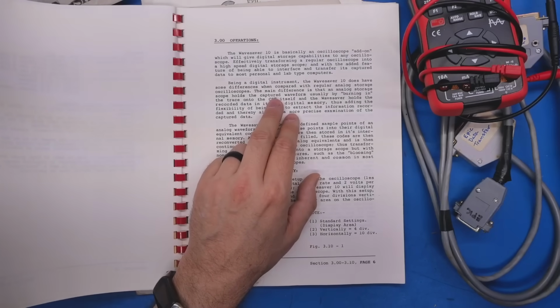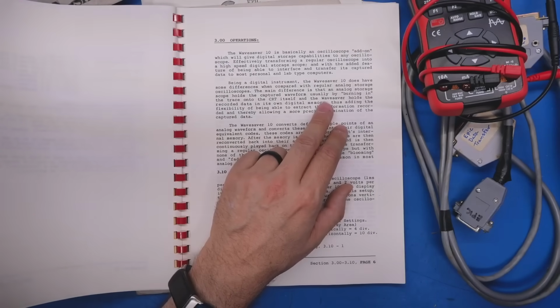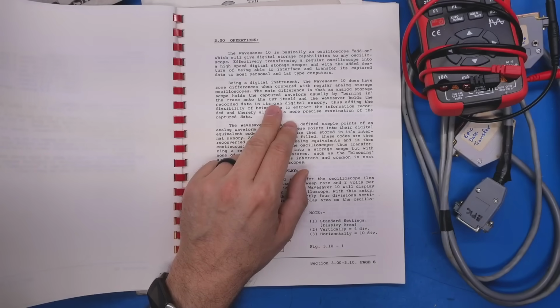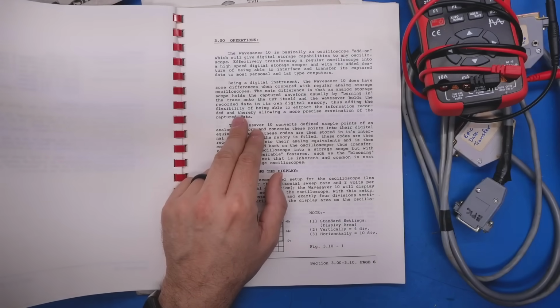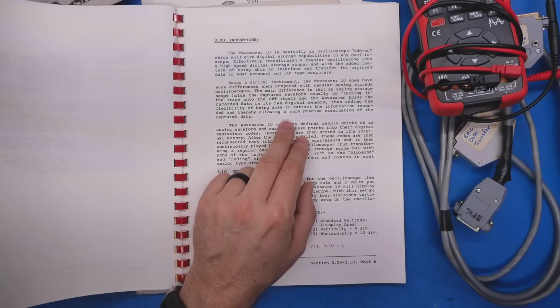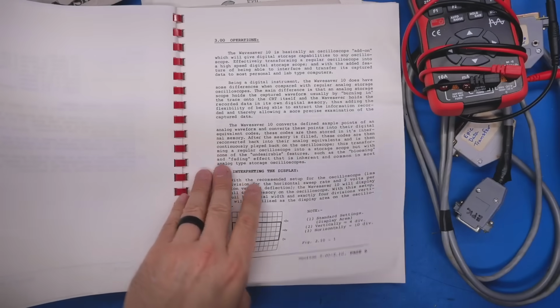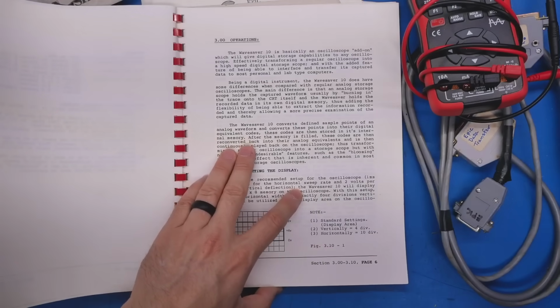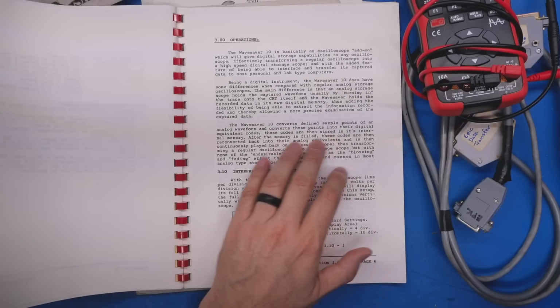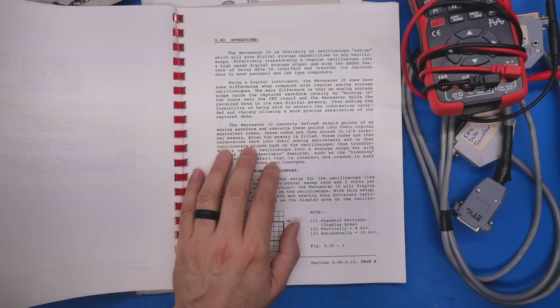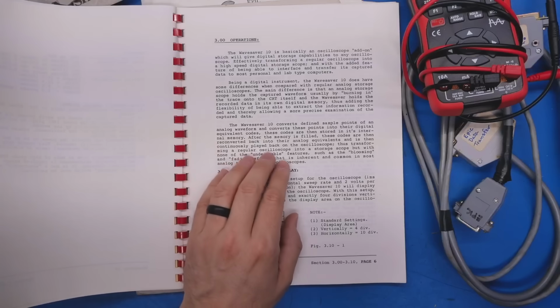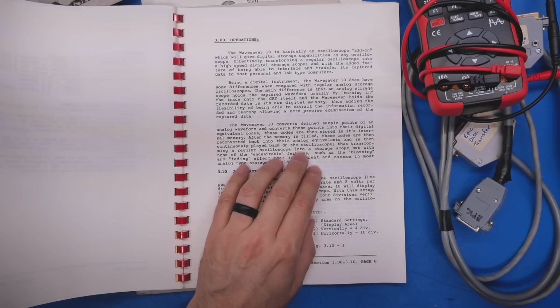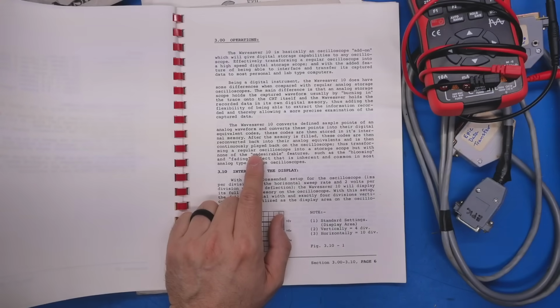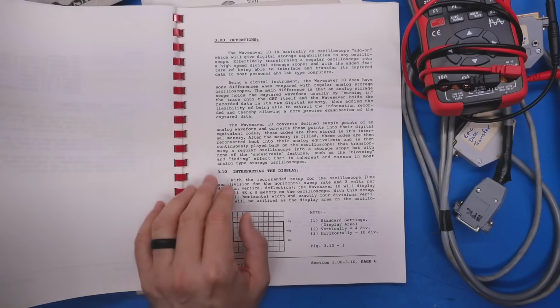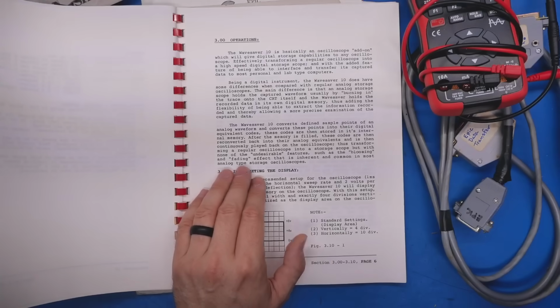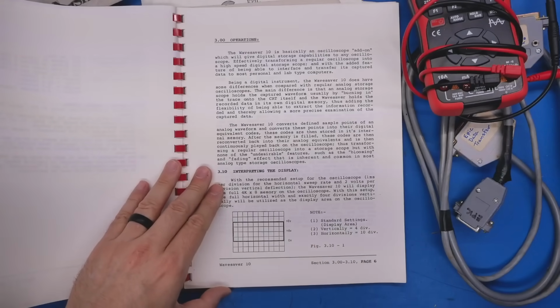And yeah, so it says right here, the main difference to an analog oscilloscope is that it holds the waveform by burning the trace into the CRT itself, while the Wavesaver holds the recorded data in its digital memory, thus adding the flexibility of being able to extract the information recorded and allowing a more precise examination of the captured data. The Wavesaver 10 converts defined sample points of an analog waveform to digital equivalent codes, and these codes are then stored in the internal memory. After memory is filled, the codes are recovered back into their analog equivalents. So this is like an output to your scope, I guess, and then is continuously played back on the oscilloscope. That's kind of what I thought was happening. Thus, it transforms a regular oscilloscope into a storage scope, but with none of the undesirable features such as blooming and fading effect that is inherent with most analog type storage scopes.